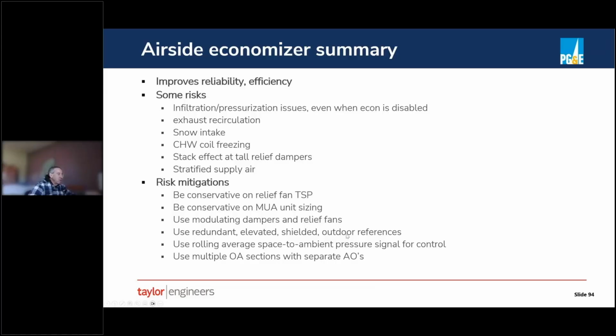Redundant, elevated, shielded outdoor air references. It can be hard to get a good outdoor air temperature. And if you have an economizer high limit switch, you want to make sure you're looking at the right temperature. Rolling average space-to-ambient pressure signal. So sometimes if it's windy, you can have a hard time getting an accurate pressure signal of the space to the ambient.